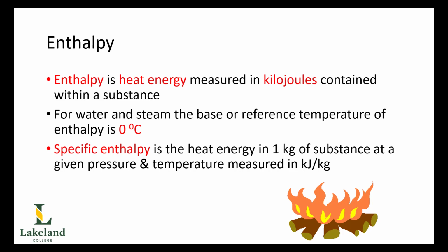Now, this is really important to know because, as we've said before, you can't put water into a boiler and then have it freeze. When water freezes, it expands by about 9%. And when that happens, we can start to burst seams or break welds within our boiler, and we can cause massive amounts of damage. So we never ever want to allow ice to form in a boiler. That's really important from an operation perspective. So that's our base temperature, because we're never going to put water in colder than 0 degrees.